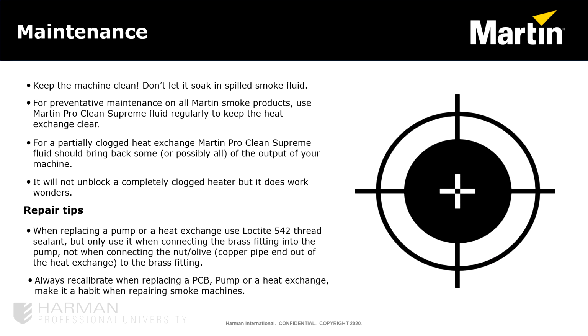The most important task to perform with maintenance is to recalibrate when replacing a PCB, pump, or heat exchange. Every heater, pump, and PCB will have a slight difference in variation of output, temperature, and housing, so it is important that calibration is done every time one of these parts is affected. Processes for calibrating heaters with a digital PCB, calibrating analog heaters, and updating firmware can be viewed in other Martin videos for the JEM products.